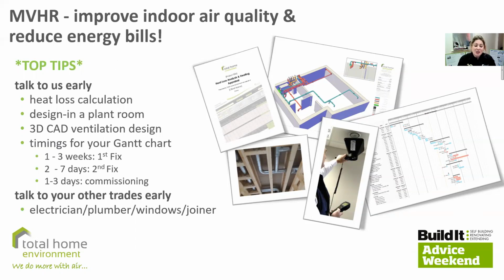Be aware for your Gantt chart that you're going to allow up to 3 weeks for first fix and up to a week for second fix. The lower figures are more to do with heat recovery ventilation, and the higher figures are to do with heat pump ventilation, and allow anything between 1 and 3 days for commissioning.